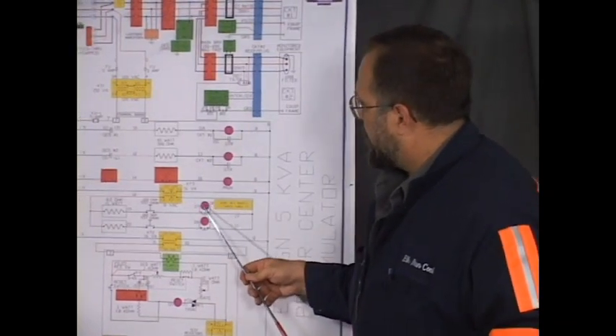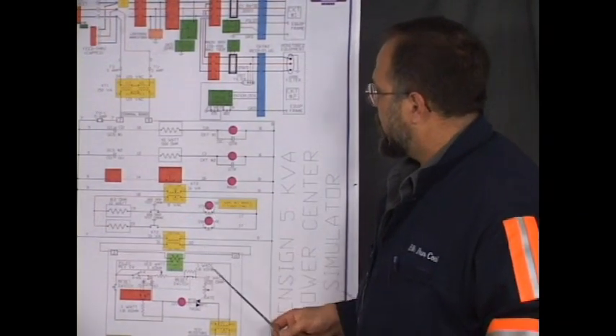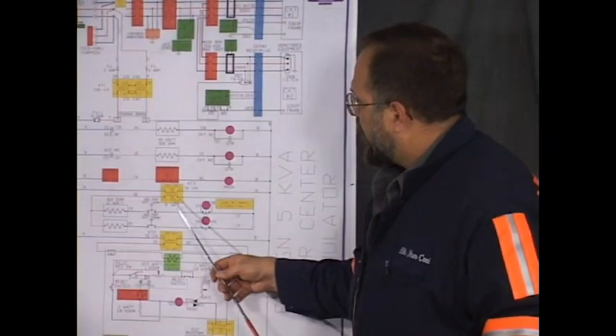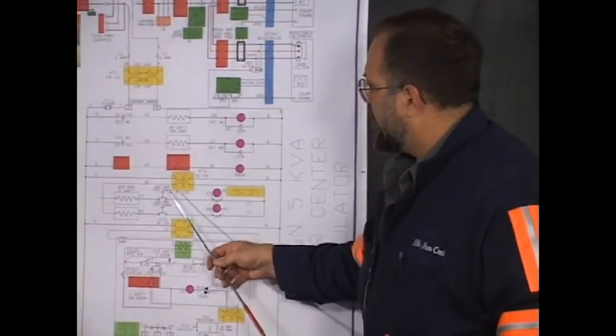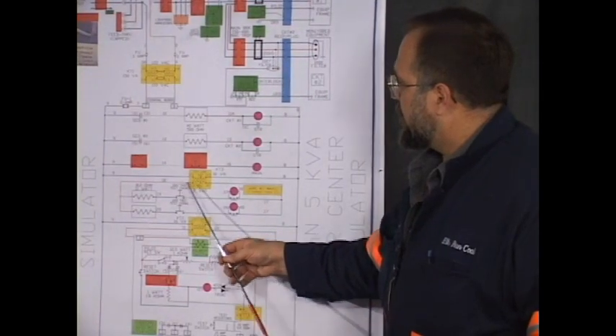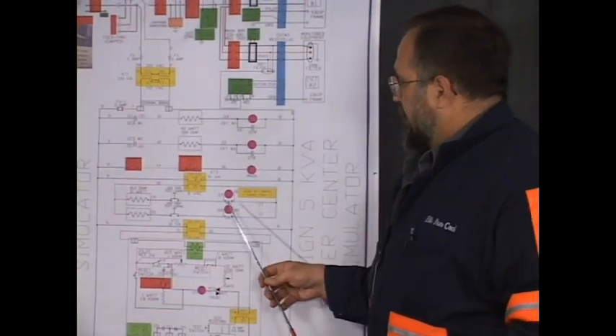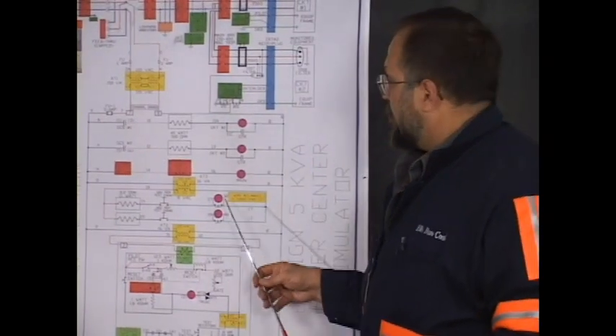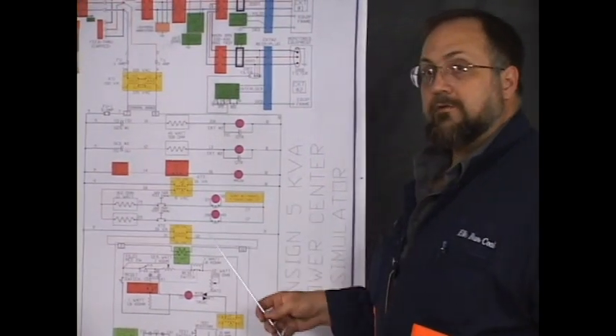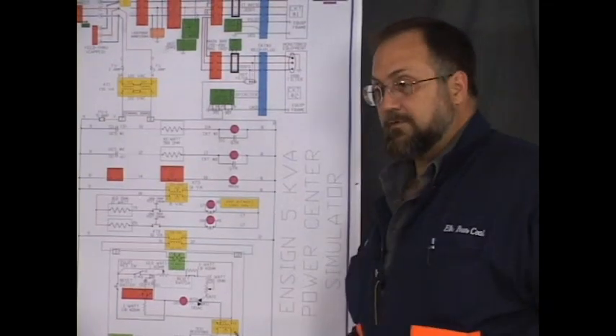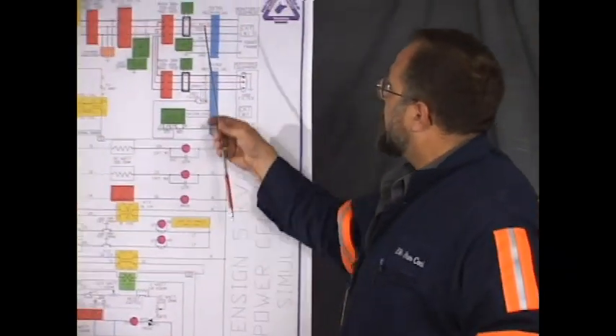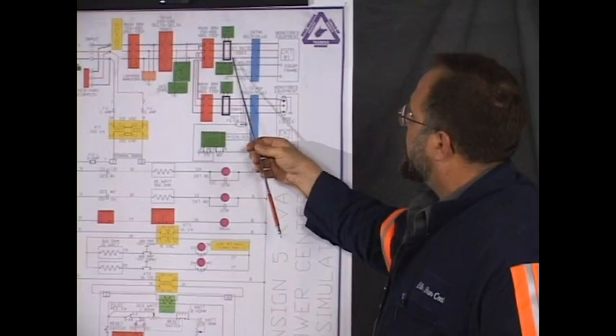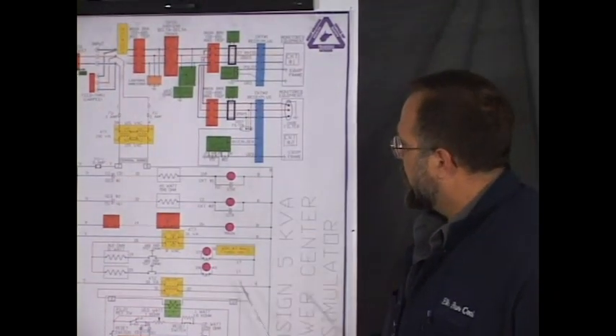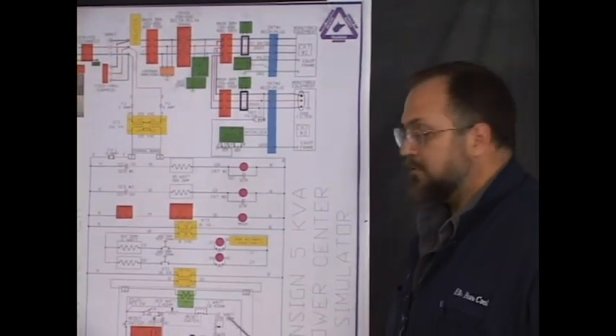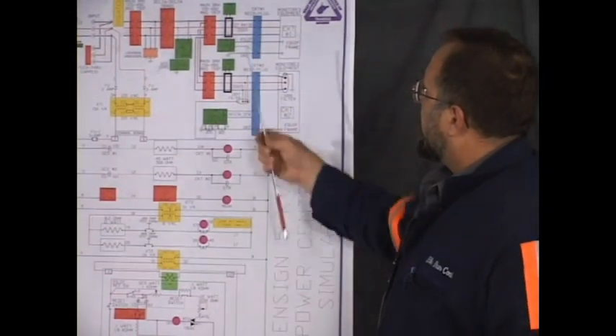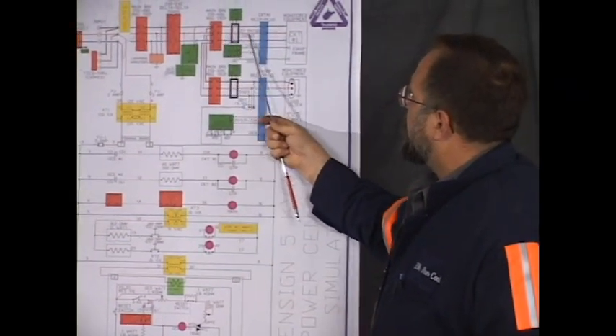You can see a couple of places where the ground trip relay is illustrated on the drawing. Right here on the ground trip test circuit, if you press the test switch making this circuit, it simulates a ground fault and operates the relay just as if you had a ground fault, to test its operation and make sure that it is indeed working. The ground trip relay here, this is the CT. This is one symbol for the CT on the power circuit. Same CT, different symbol on the control circuit. Okay, the power conductors are routed through the CT.